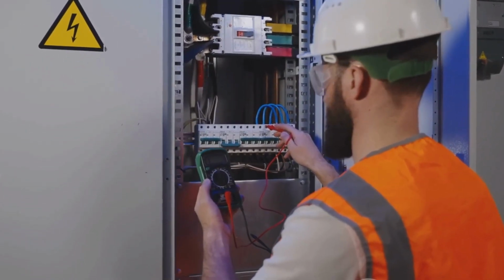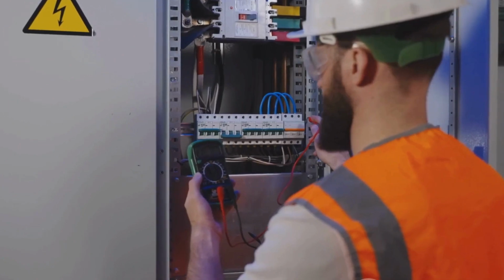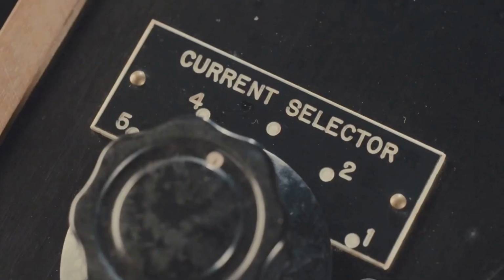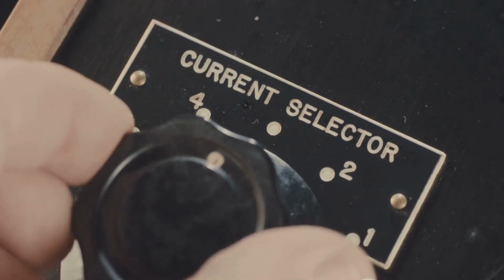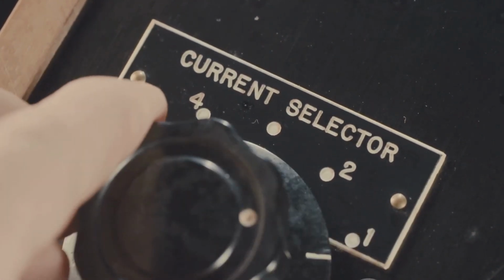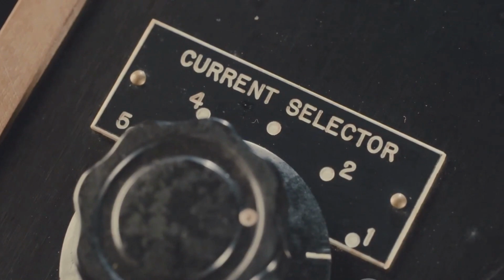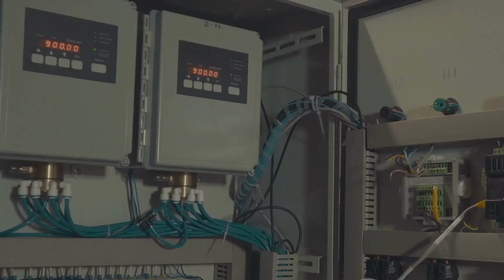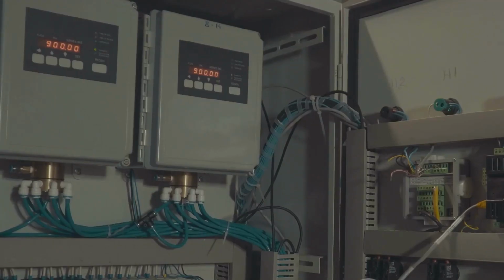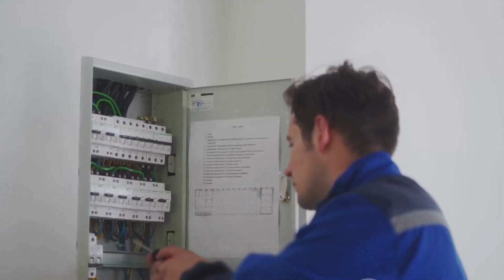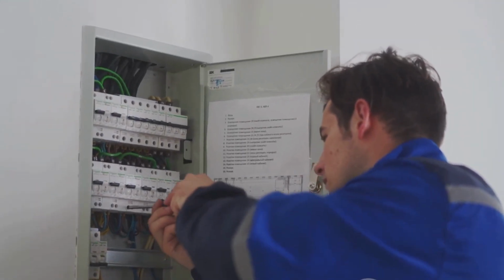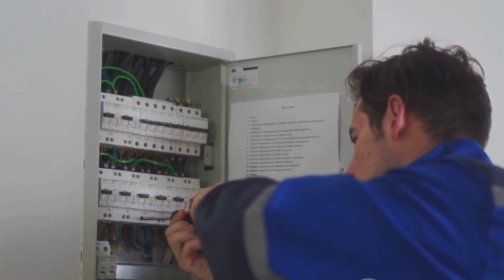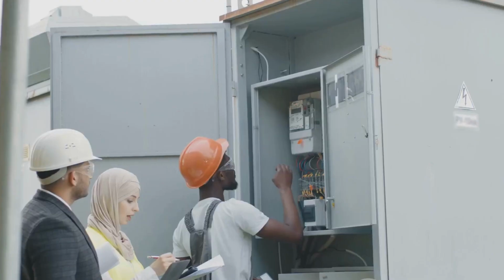On the flip side, isolators are the strong, silent types. Their operation is based on physically disconnecting the circuit. Simpler in design compared to circuit breakers, they're manually operated, requiring a hands-on approach. And unlike the marathon running circuit breakers, isolators are more like sprinters. They're not intended for frequent operations. Instead, they come into play during planned maintenance, taking a breather until the next maintenance cycle rolls around.